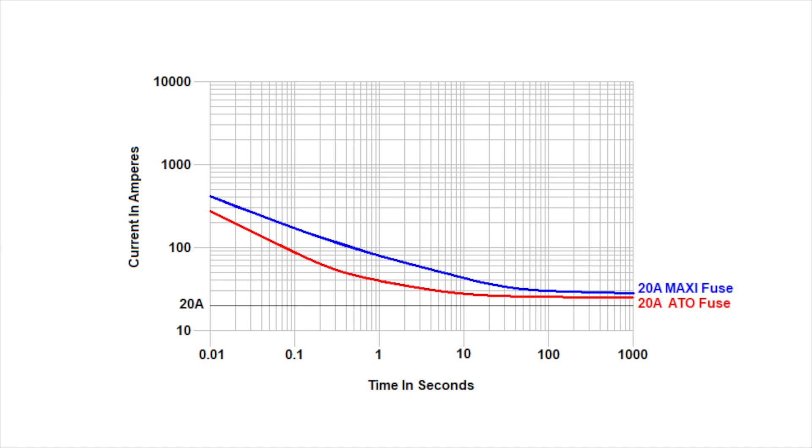When we compare the TC chart for a slow blow fuse with a standard fuse, we see that the performance curve in the 10 second and greater range is fairly close. But in the area between 100 milliseconds and 10 seconds, the slow blow fuse allows more amperage.